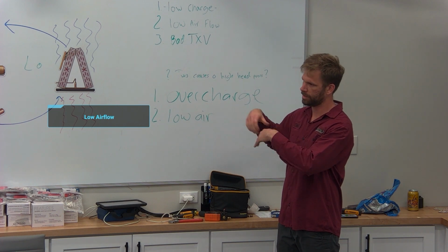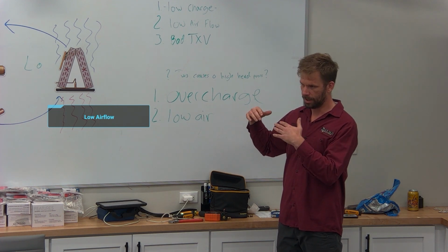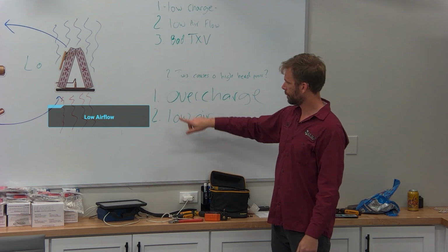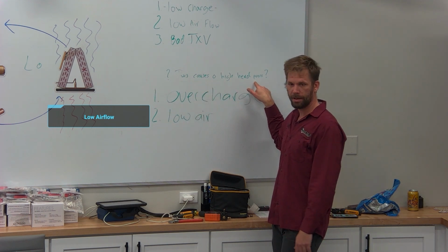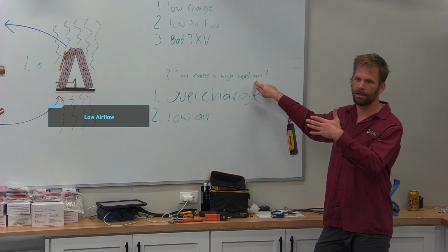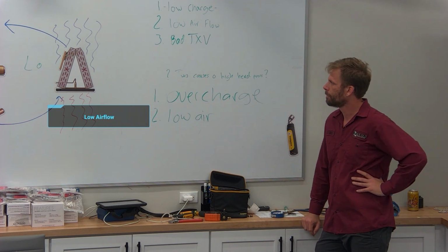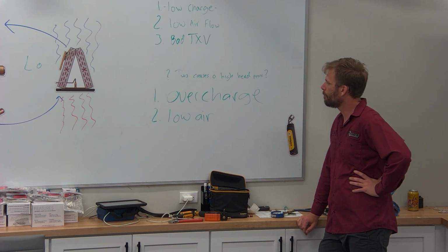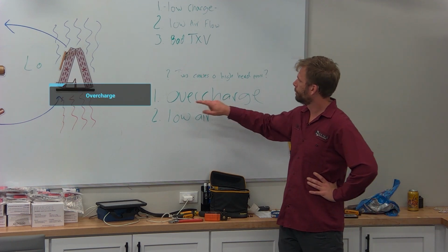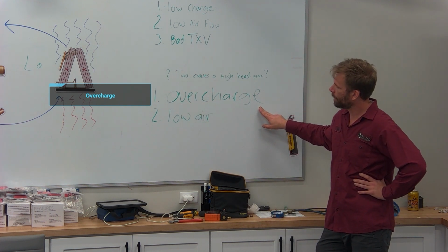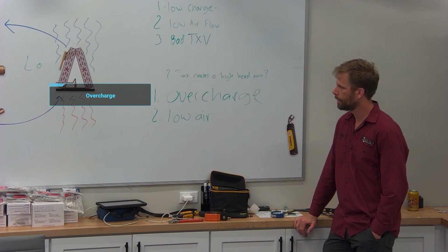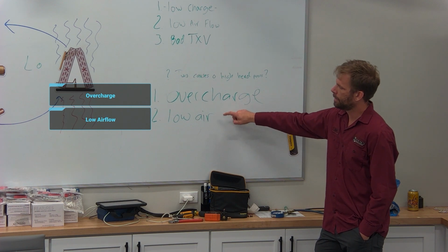So low airflow means it's not rejecting as much heat. We know that if it doesn't get rid of its heat, then that high temperature creates high pressure. So we're gonna have a higher pressure. We're gonna have a high head, higher than normal. We're not getting rid of our heat. We're dealing with higher temperatures, right? But at the same time, we could have overcharge happening, but it's not because of low airflow. It's not because of really hot coils. We've added too much refrigerant. So how could we test to find out the difference between which of those two is causing the problem?